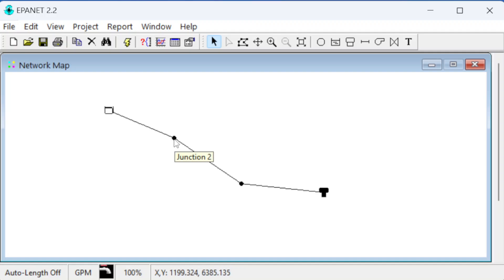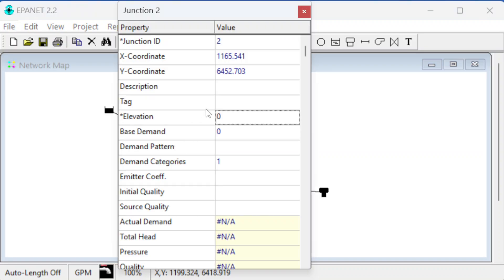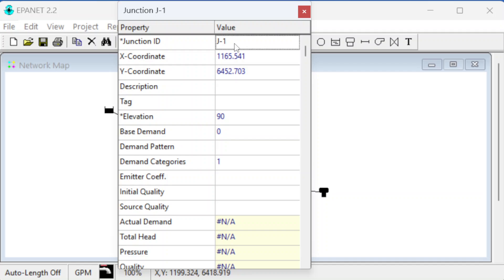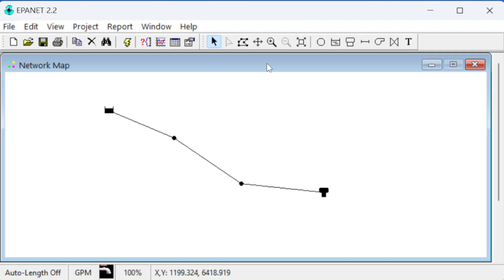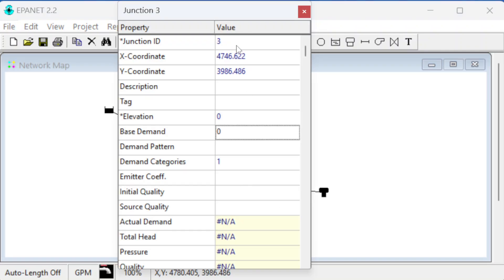For the junctions we need to enter elevation and demand. The first junction has elevation 90 — we'll call it J1 — and it has a demand of 100 gallons per minute. The demand units match the overall flow units we specified. Close that, then go to the next junction and call it J2.